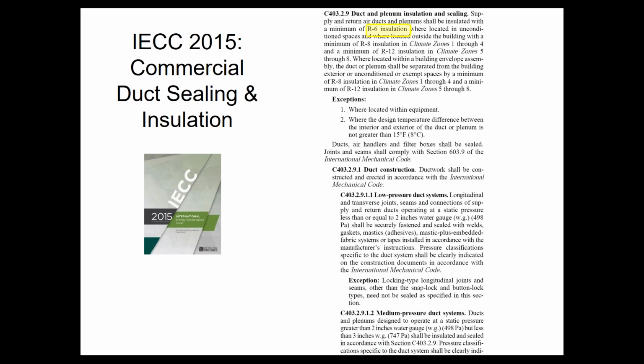So from a code perspective, just like residential, ducts have to be sealed, ducts have to be insulated. If the duct is in an unconditioned space, it's got to be R6. If it's outdoors, it's got to be R12. The climate zones that we care about, which are 5 and 6 for today's purposes.